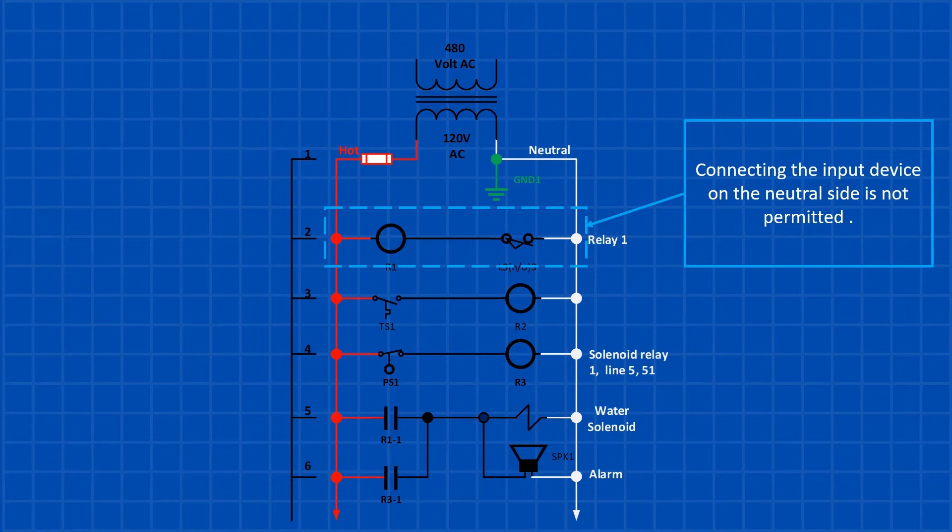Even though the circuit will work, it is an improper design and not code compliant to connect the input devices to the neutral and output devices to the hot side of the ladder.